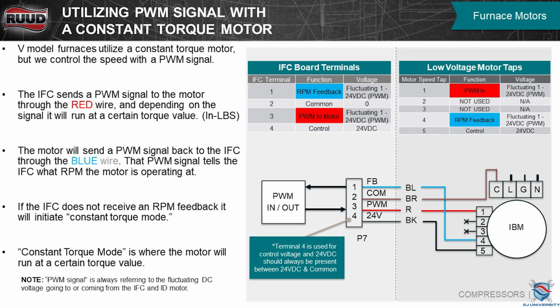A little bit on how to check this. So if you're troubleshooting this, you're going to have 24 volts DC between here and common, constant. Okay? Between PWM and common, you should be getting 1 to 24 volts DC fluctuation. Between your blue wire, which is your feedback wire, and common, you should be getting 1 to 24 volts DC. That's how you check this motor. You no longer use a motor tester.